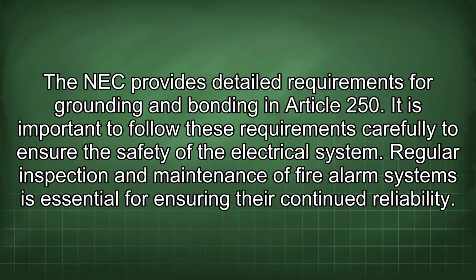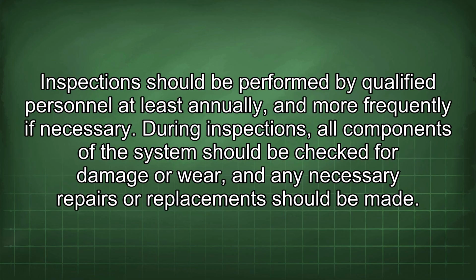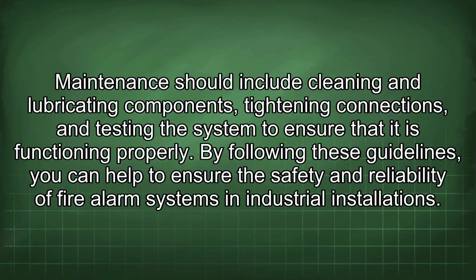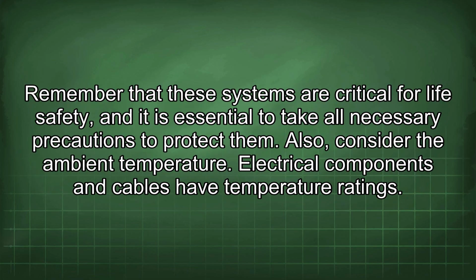Regular inspection and maintenance of fire alarm systems is essential for ensuring their continued reliability. Inspection should be performed by qualified personnel at least annually and more frequently if necessary. During inspections, all components of the system should be checked for damage or wear, and any necessary repairs or replacements should be made. Maintenance should include cleaning and lubricating components, tightening connections, and testing the system to ensure that it is functioning properly. By following these guidelines, you can help to ensure the safety and reliability of fire alarm systems in industrial installations. Remember that these systems are critical for life safety, and it is essential to take all necessary precautions to protect them. Also consider the ambient temperature.